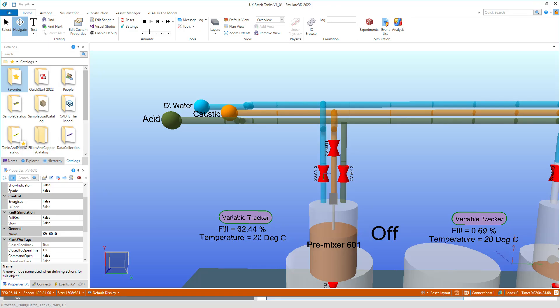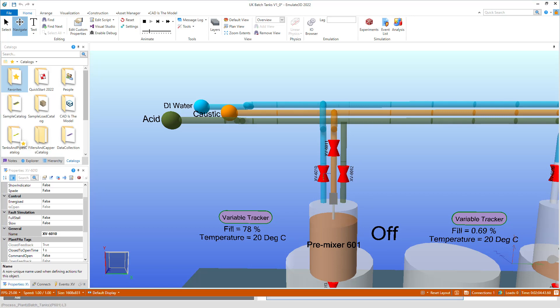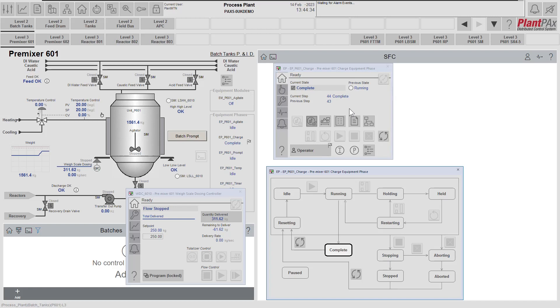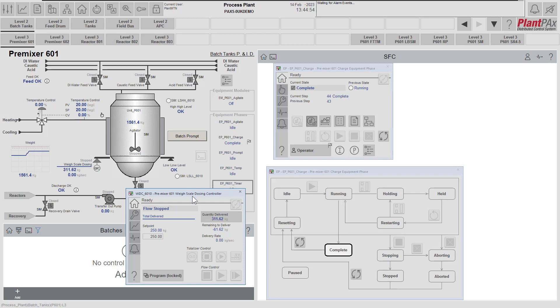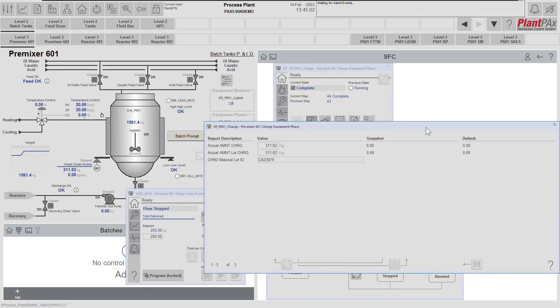I'm going to switch back to the Emulate 3D view so you can watch the plant emulation. Here you can see the valve has been commanded to open — Emulate 3D has responded, after the valve transit time the caustic was added to the tank, and its level went up. Going back to the operator workstation, we can see that the charge phase completed, closed the valve which we saw in Emulate 3D, and it's now moved to the complete state. The dosing controller had a set point of 250 but we delivered 311 — again an intentional overshoot for demonstration purposes. The report values show the actual amount charged along with the lot ID of the caustic that was charged.